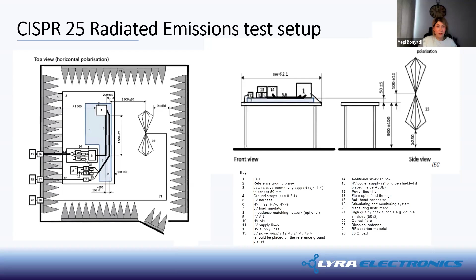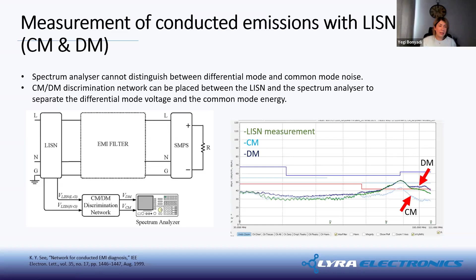Spectrum analyzers are normally used to measure the emissions, but they cannot distinguish between common mode noise and differential mode noise. In this slide, I'm showing you the difference if you use a discrimination network between your LISN and the spectrum analyzer. You can separate common mode from differential mode noise. In the graph on the right-hand side, you can see how this is shown, and it helps a lot when you're trying to troubleshoot your device. If you're failing, for example, between let's say 80 to 100 megahertz, you can separate them to know if it's more common mode noise or differential mode noise, and then design your filters according to that.